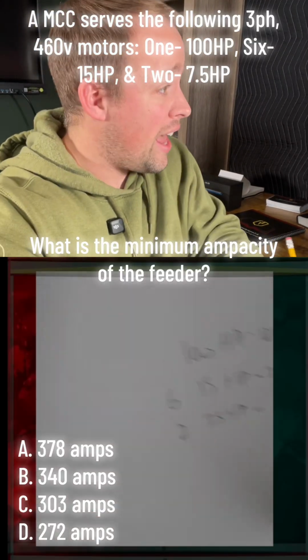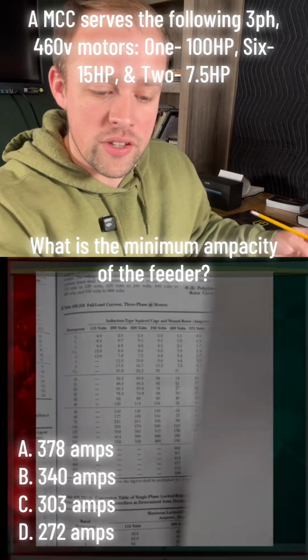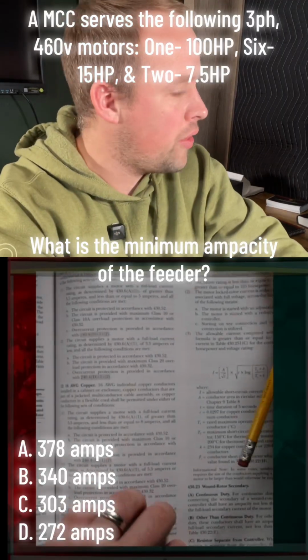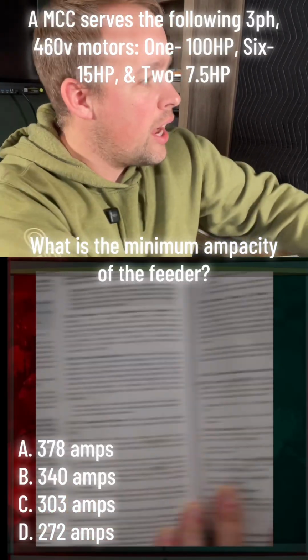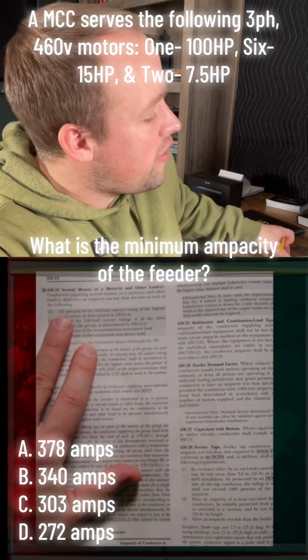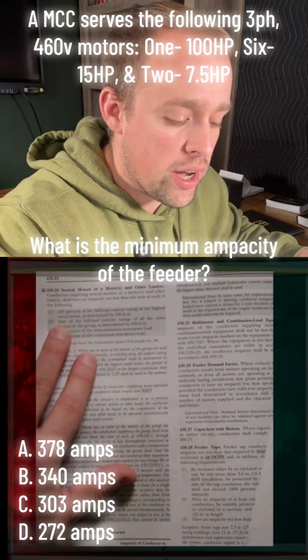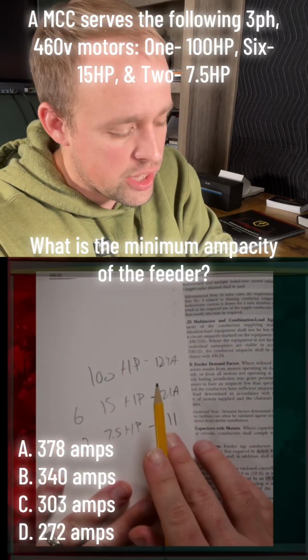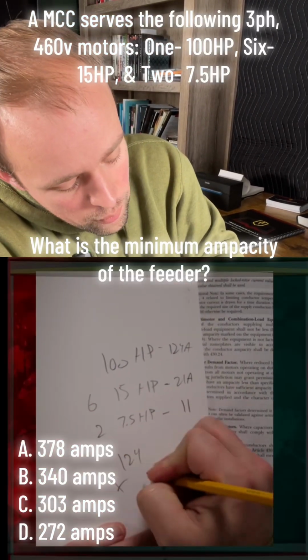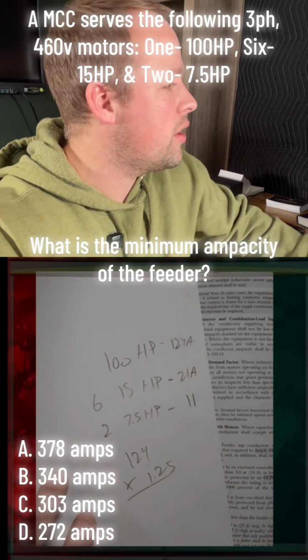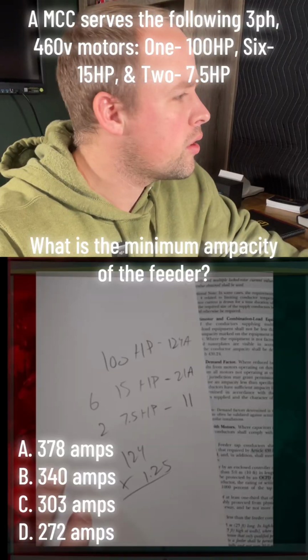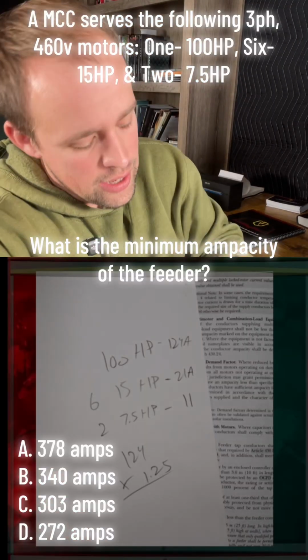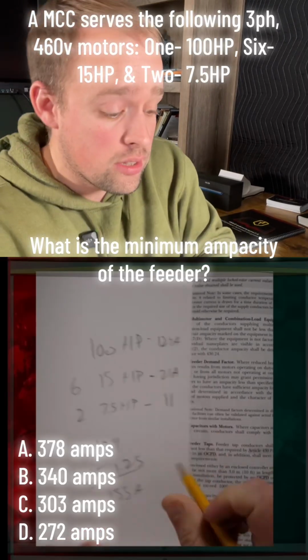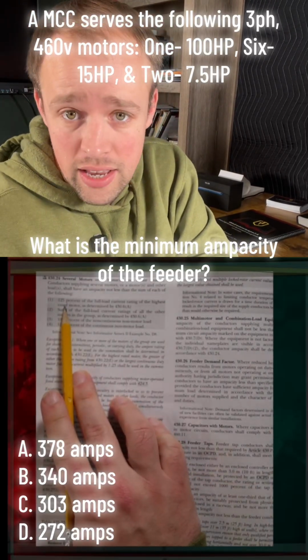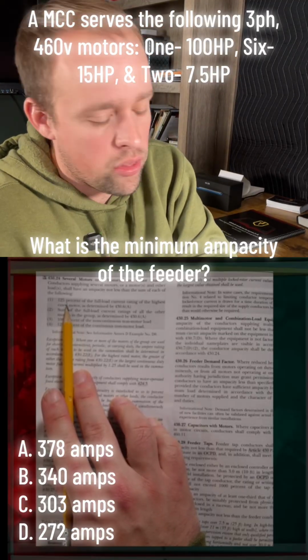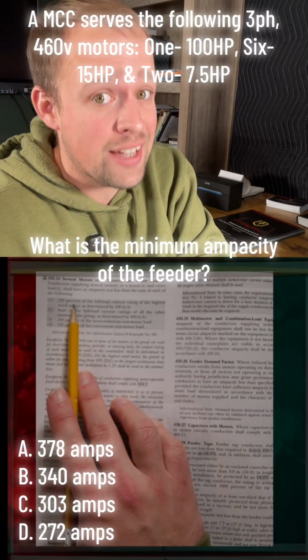Now that I have all my full load currents for all of these motors, let's go back to that code article that specified what we need to do here. So again, number 1 says 125% of the full load current rating of the highest rated motor. What's the highest rated motor? That's my 124. So 124 multiplied by 1.25 is 155 amps. So that covers number 1, 125% of the full load current of the largest motor, which is specifically the ampacities in the code book.